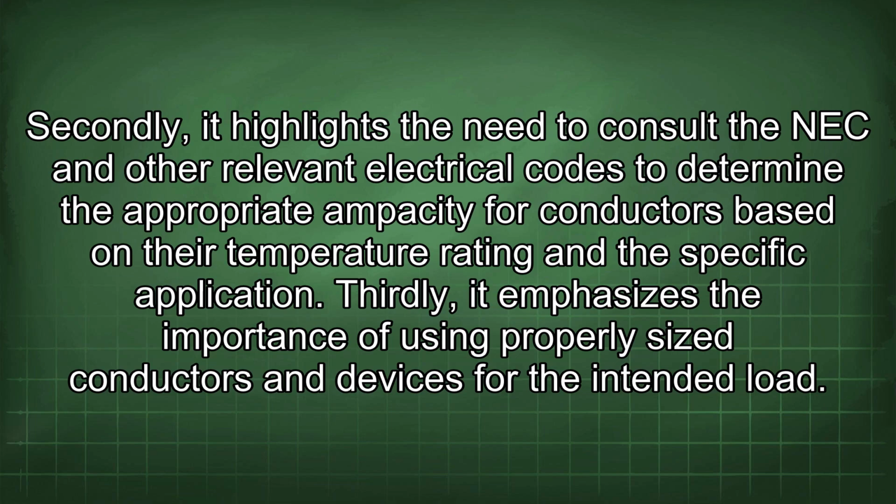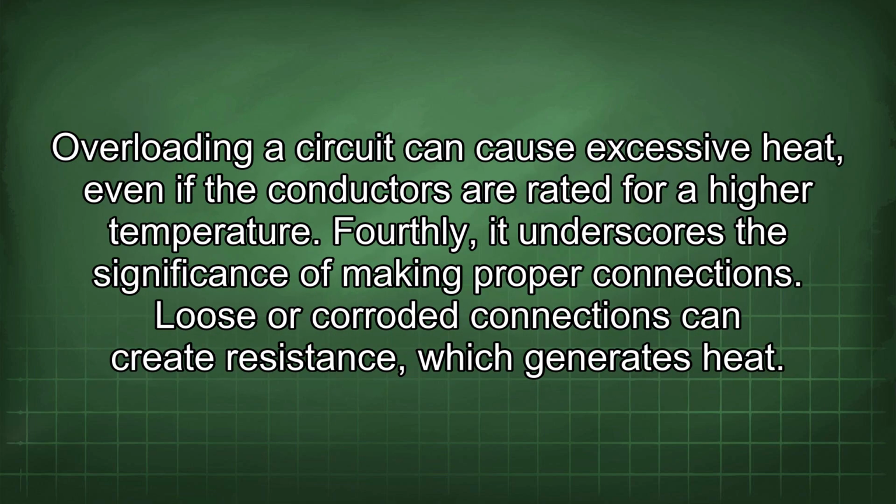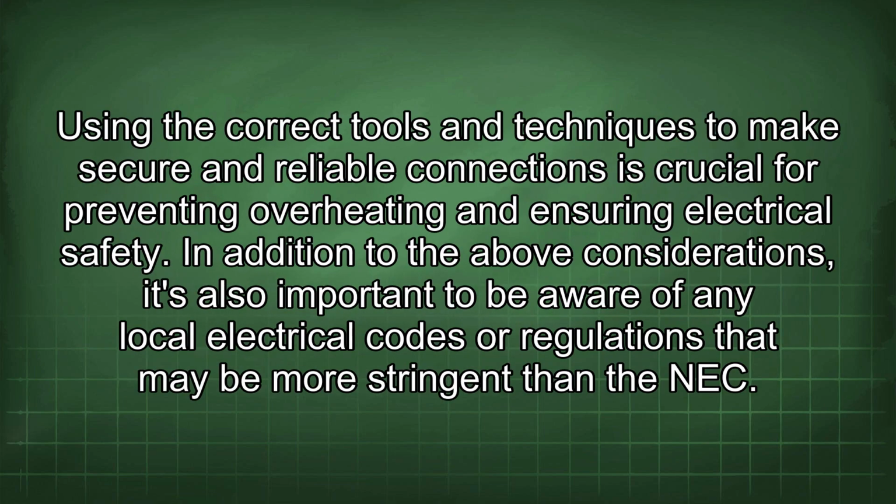Thirdly, it emphasizes the importance of using properly sized conductors and devices for the intended load. Overloading a circuit can cause excessive heat, even if the conductors are rated for a higher temperature. Fourthly, it underscores the significance of making proper connections. Loose or corroded connections can create resistance, which generates heat. Using the correct tools and techniques to make secure and reliable connections is crucial for preventing overheating and ensuring electrical safety.